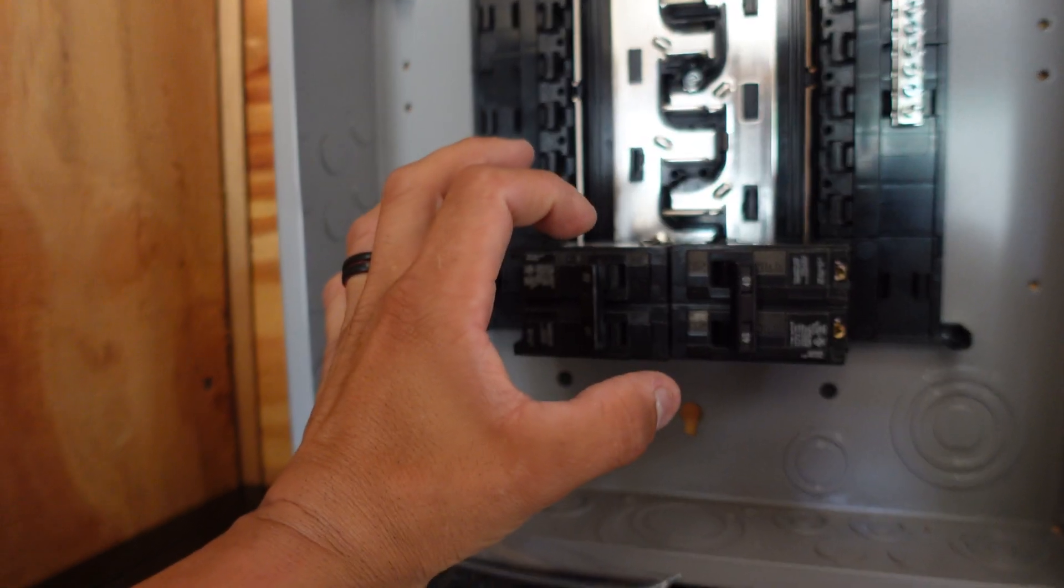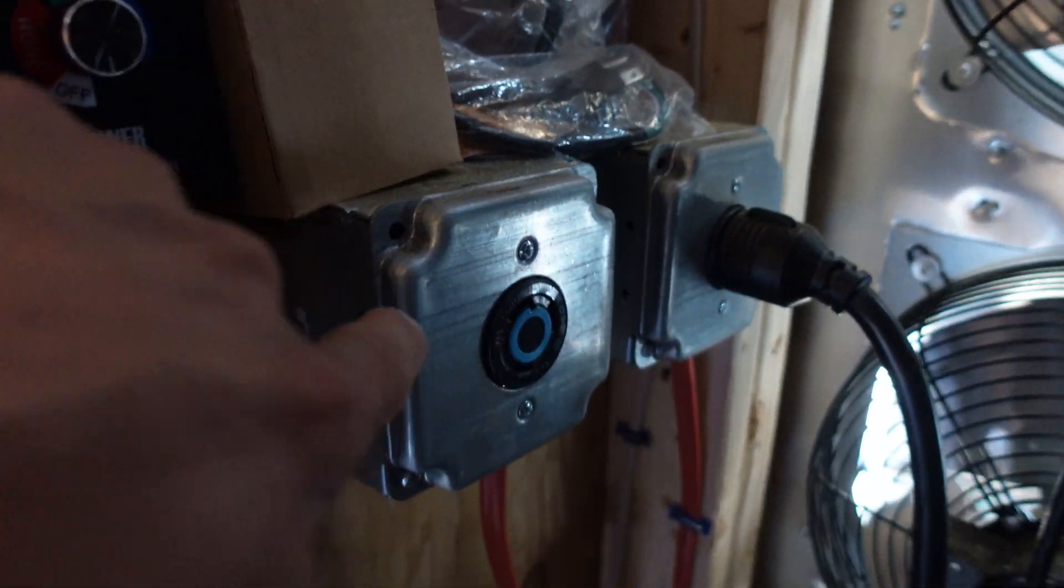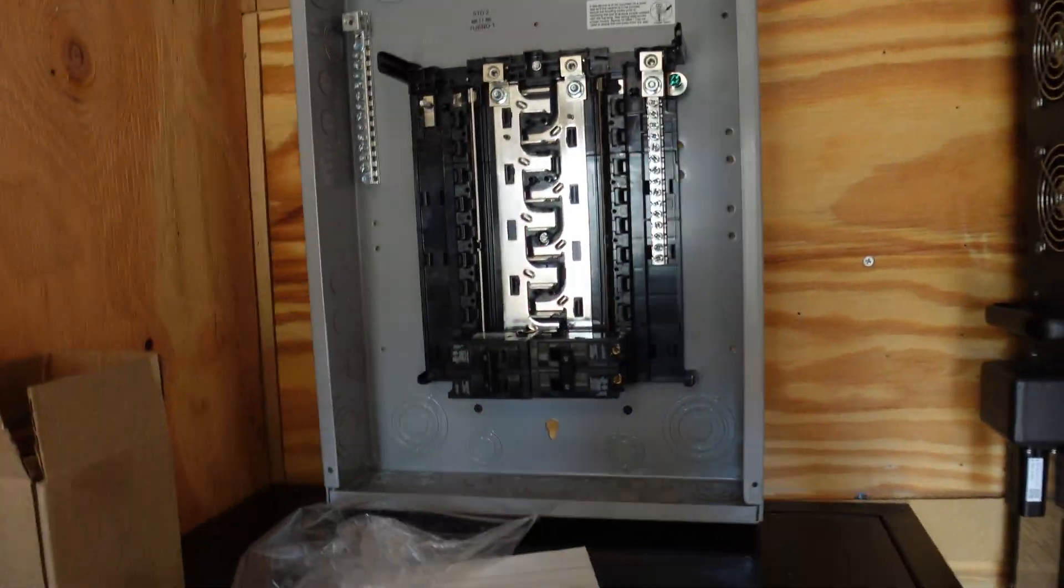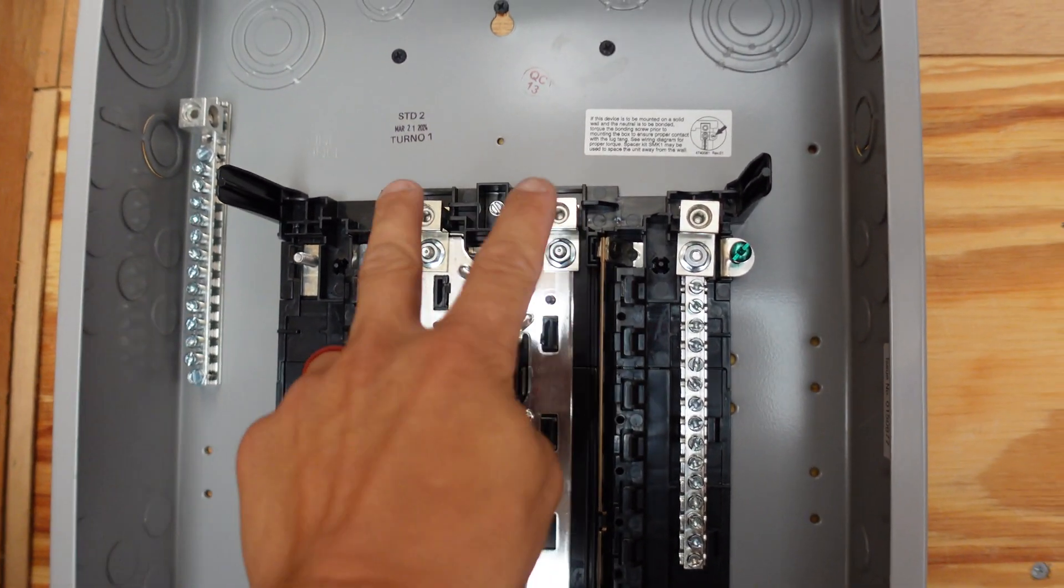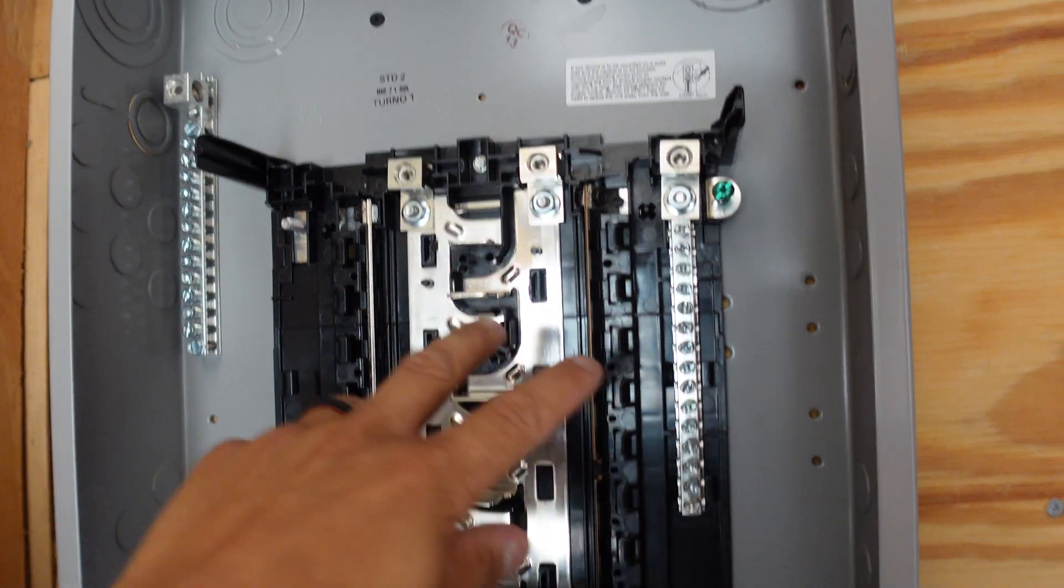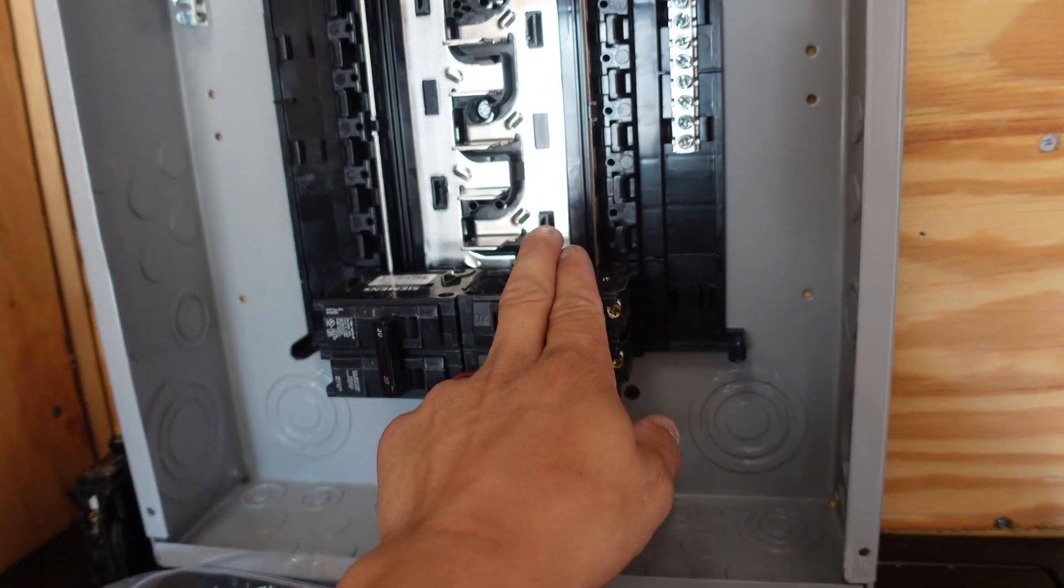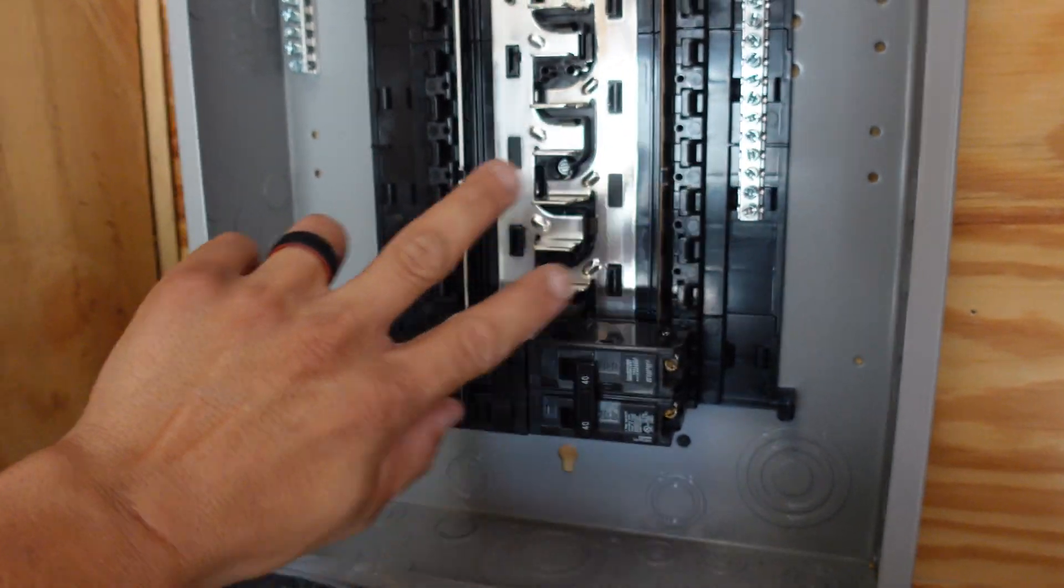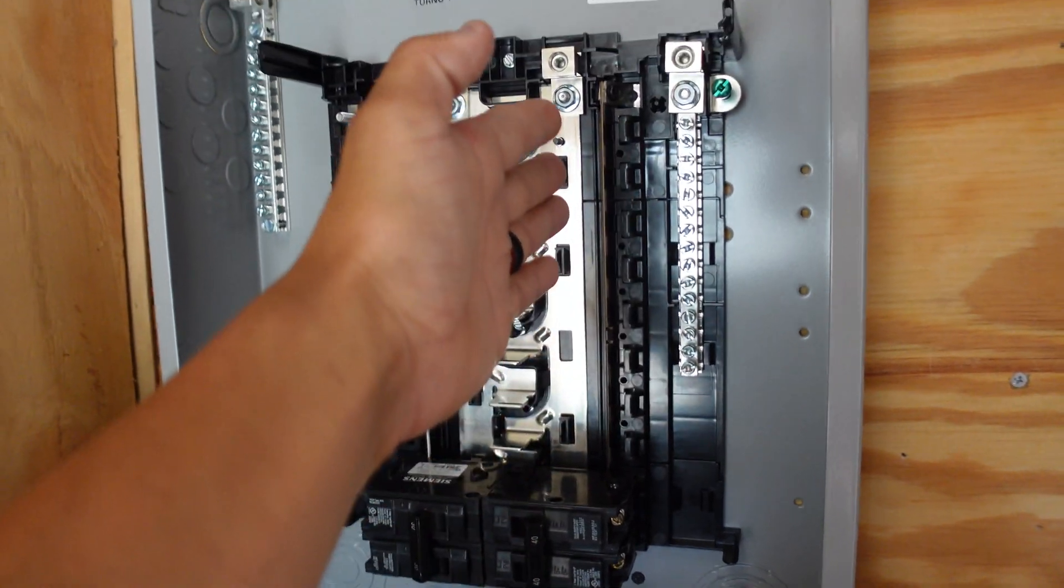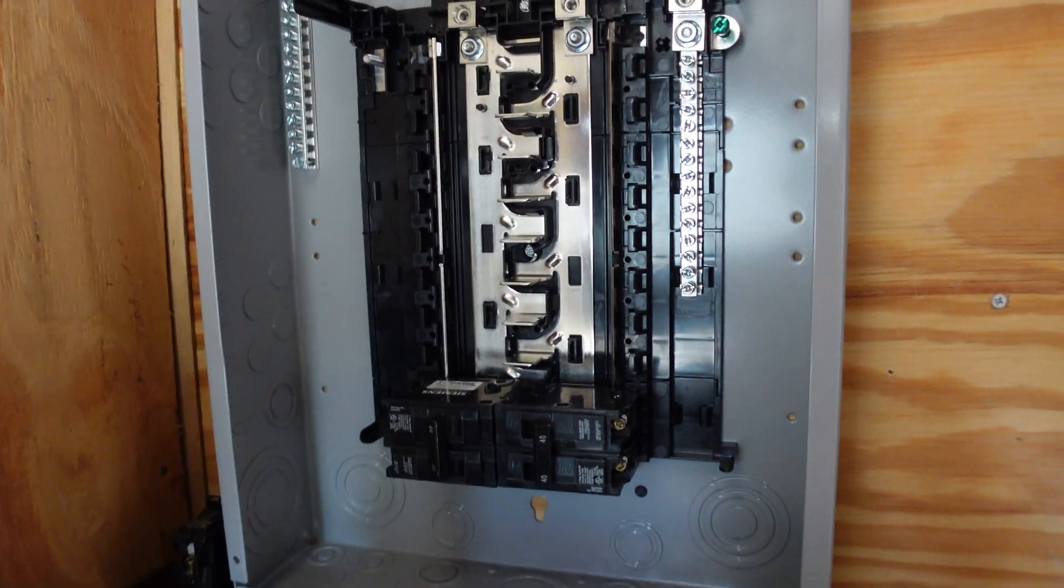Alright, now those are all pushed in all the way. So again, inverter going into this one, 30 amp going into this one. That's gonna be one of them circle plugs, right, a 30 amp plug for a PDU that I have. Now the reason I'm doing things like this and I'm not running the legs up to the actual top lugs right there where the wires typically would come in, is because if I ever add another inverter I could just throw in another 40 amp breaker here and wire it to the inverter that way. Then I have that one which will backfeed the panel as well. I'm using this as like a load center. I only have one inverter for right now, so there's no reason to like separate this if that makes sense.